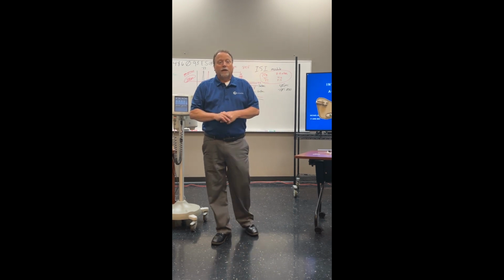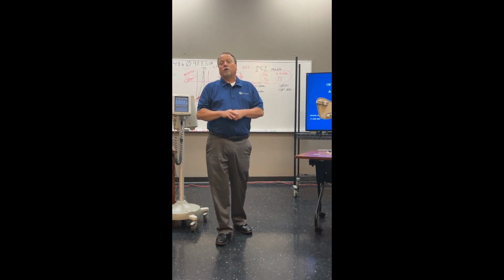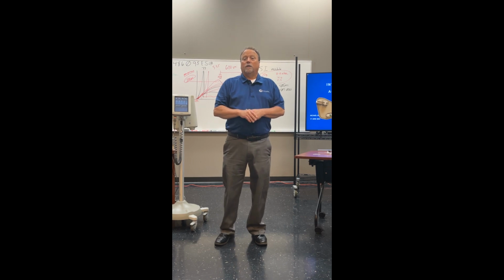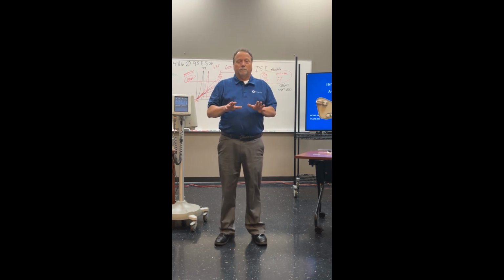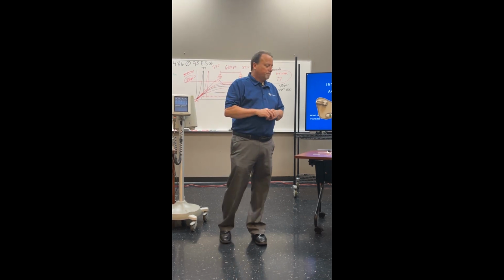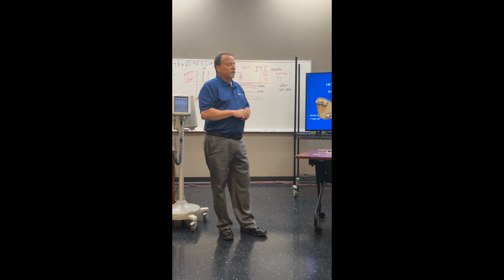Now, they do make an Empower MR injector, but that is hydraulic driven, and it's a little bit more complicated, but yet simplified. Servicing it is complicated because you're dealing with hydraulics and you have to bleed it and purge it, so we really don't get into that injector. To be honest with you, that Empower MR is a really solid unit. Very minimal problems with that unit. So let's start off with the CVi injector.